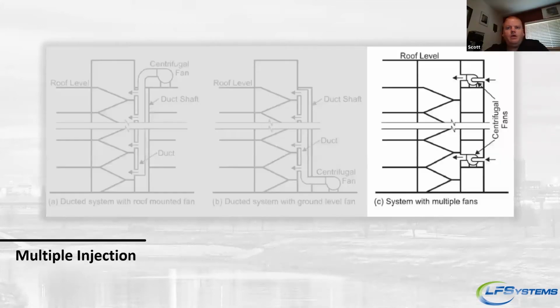Very good. Another type of multi-point injection that you might see is used in very tall buildings, where you have a series of smaller centrifugal fans in zones. So instead of relying on one very large fan to pressurize an entire stairwell, you may have smaller fans placed along the rise of the stairwell itself.